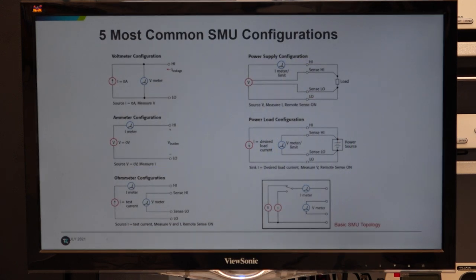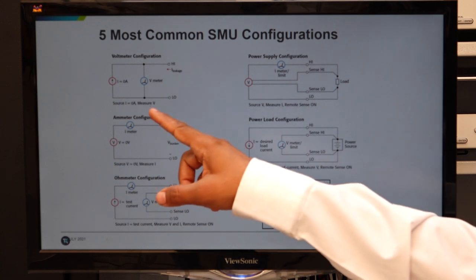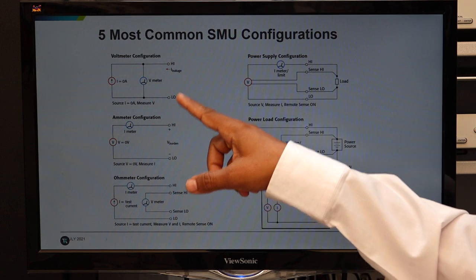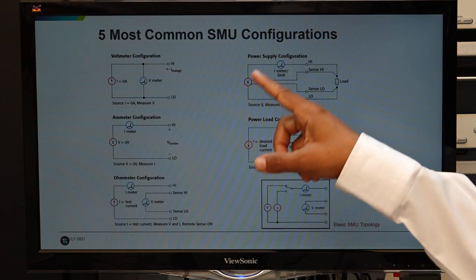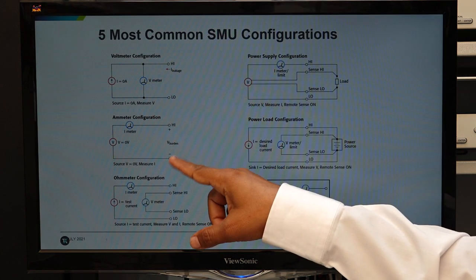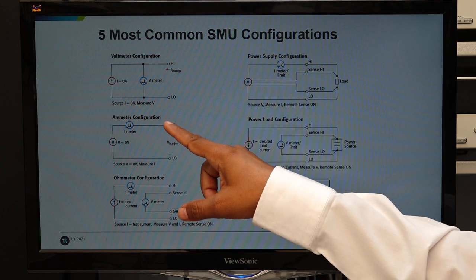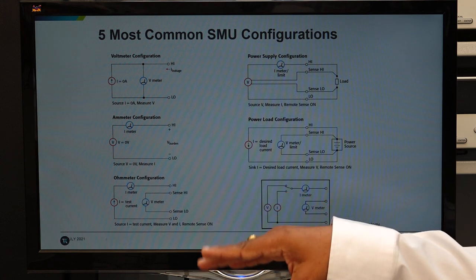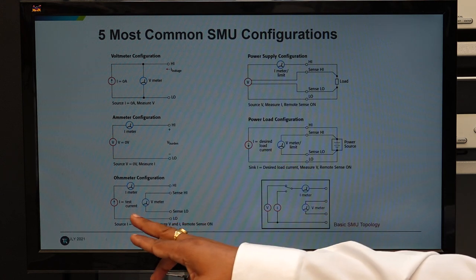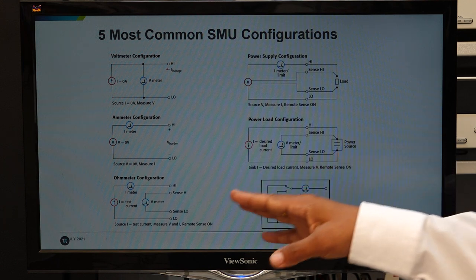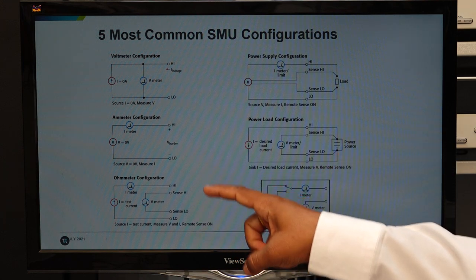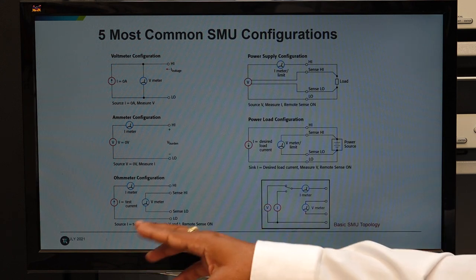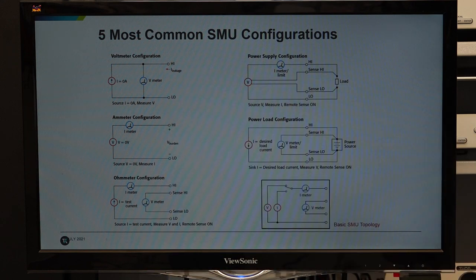For example, we can use SMU as a high accuracy voltmeter in which zero current will be sourced and voltage measurement will be done. We can also use it as an ammeter in which the voltage source comes by sourcing zero volts while we are measuring current. We can also use it as an ohmmeter like a DMM in which a known value of current can be sourced to the device and voltage can be measured in two-wire or four-wire mode.